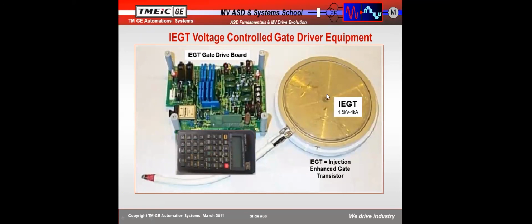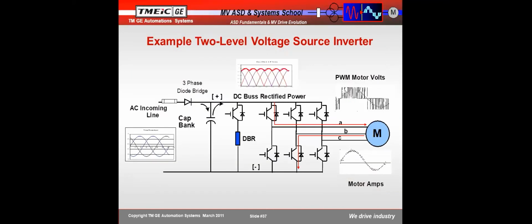I like pictures better, you might be able to tell. That's an IEGT, and you can compare it to a calculator there. Look how small that is, and that can do 4,500 volts and 4,000 amps. It's amazing that any device can do that. And if you buy a 1,000, 2,000, 3,000 horsepower drive, you're not going to get IEGTs because you can't afford them. But when you get into very large, north of 10,000 horsepower, then you may be in the range where you can afford to use IEGTs. And that's kind of, to me, the latest and most amazing device available.